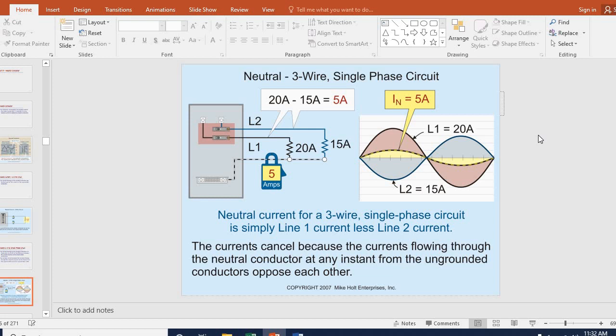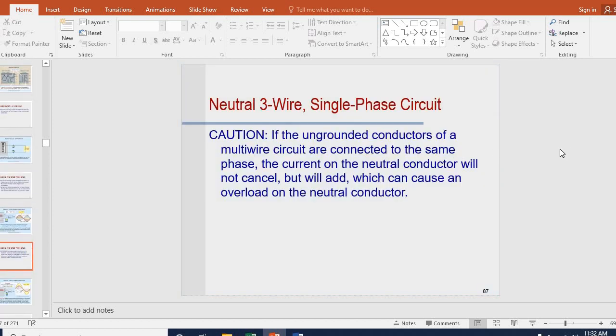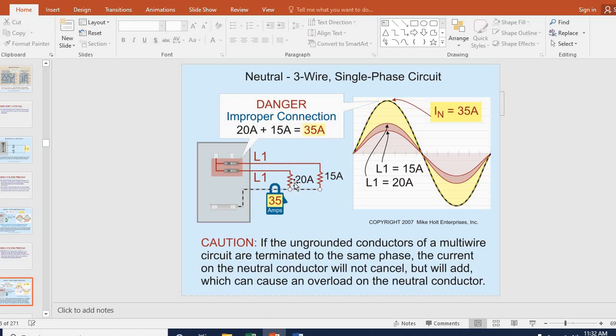There's the neutral for a 3-wire single-phase circuit. These are some good examples of looking at that neutral. The currents cancel because the currents flowing through the neutral conductor at any instant from the ungrounded conductors oppose each other. If the ungrounded conductors of a multi-wire circuit are connected to the same phase, the current on a neutral conductor will not cancel but will add, which can cause an overload on the neutral conductor. So you have to be careful of how many neutrals are on the same circuit. So right here, if they're on different circuits, they'll cancel out.